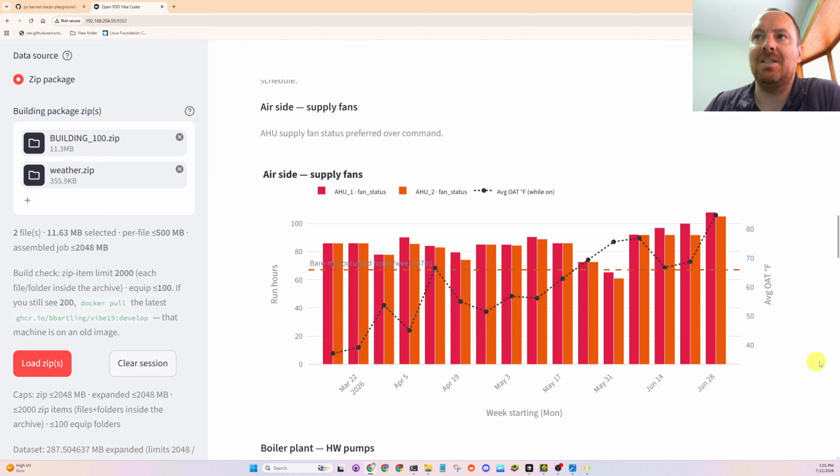Some building automation manufacturers have the algorithm built into the building automation system for optimal start, and then in research, like Pacific Northwest National Labs, there's research out there on the different kinds of mathematics on how to calculate recovery rates. So that's like upper graduate mechanical engineering theory. It's really hard to get it right and then have it working right.